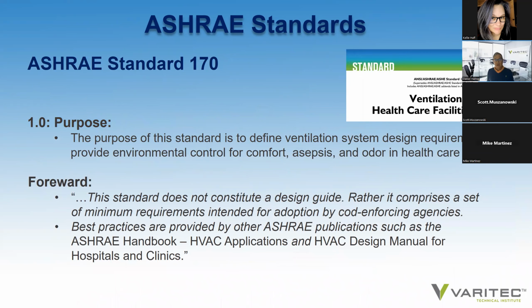And then for hospitals, ASHRAE standard 170 really defines the standards for hospitals, the conditions of operating rooms, patient rooms, whether or not there are patient rooms that are AII, airborne infectious isolation rooms, or protective environments for patients who have compromised immune systems. So standard 170 defines the conditions of healthcare facilities.